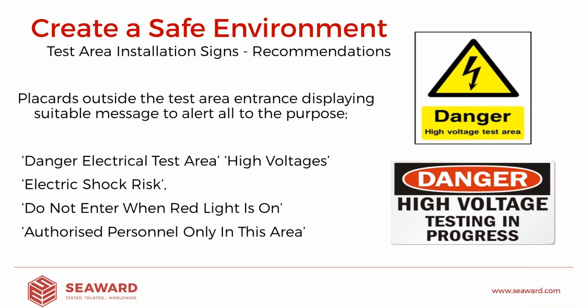They know they can't go in during a red light scenario. But we may have visitors, we may have other contract staff working in there. So we should always make sure that the area itself is significantly signed so people know exactly what's going on there, and ultimately they know it's not an area that they should be entering. So you'll see a couple of examples: danger, high voltage test area, do not enter when red light is on. All of these signs will make it very clear to anyone that maybe hasn't had training that that area is just simply off limits to them.